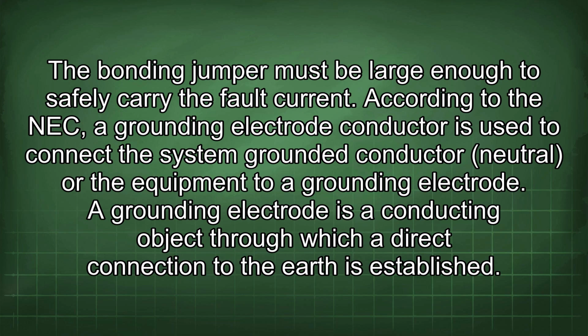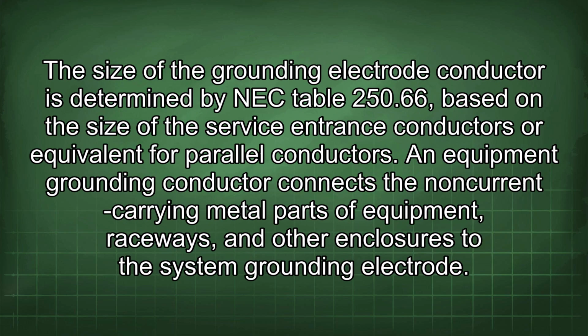According to the NEC, a grounding electrode conductor is used to connect the system grounded conductor (neutral) or the equipment to a grounding electrode. A grounding electrode is a conducting object through which a direct connection to the earth is established. The size of the grounding electrode conductor is determined by NEC Table 250.66, based on the size of the service entrance conductors or equivalent for parallel conductors.